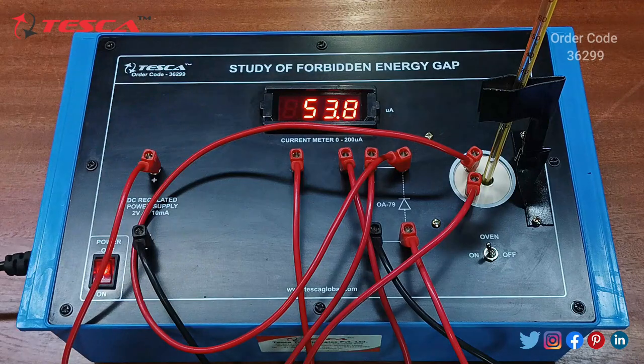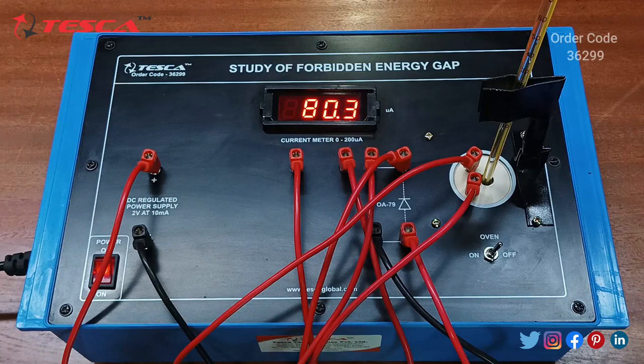From the current meter we take readings. As the temperature rises, you can see the current incrementing. Once the temperature reaches 90 degrees Celsius, turn the oven switch to the off position. Then, as the temperature decreases, take the current readings and form the observation table.